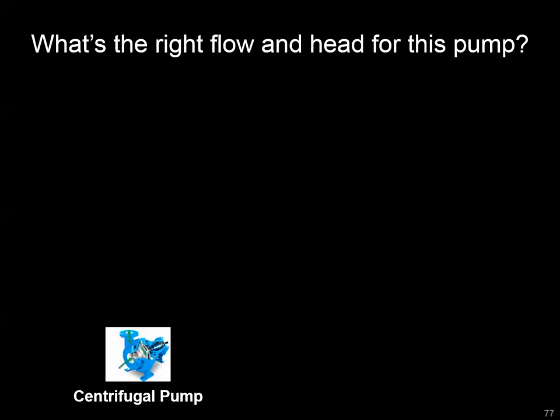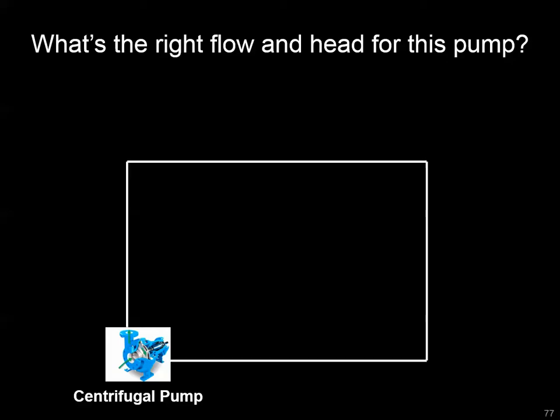How could you tell, looking at this pump, what the flow and head should be for this system? We talked about the pumping equation and how the key operating parameters you would plug into that would be the flow and the head or pressure. It's important to remember that the pump is part of a system that includes its distribution, and what's included in that distribution loop is really going to set what that flow and head need to be.